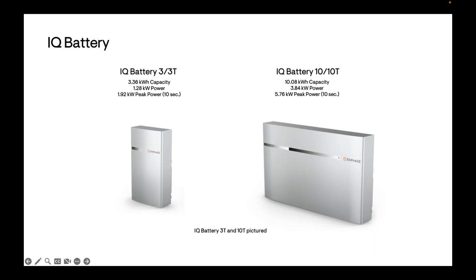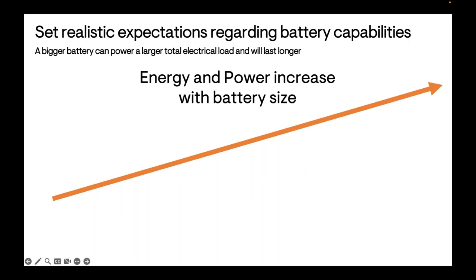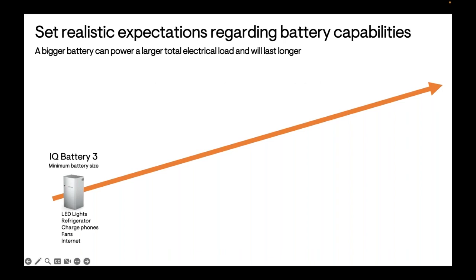When setting expectations with your homeowner, it's important to be realistic. If they try to power too many things, the system is likely to collapse and you'll get a phone call. In order for them to have a good experience and refer you more business, set realistic expectations. The IQ Battery 3 alone requires keeping electrical loads to a minimum — it's really meant as a building block, not a standalone solution for most homes. It can work if the customer just wants to power a couple of small devices: efficient LED lights, a modern refrigerator, phone charging, or fans.